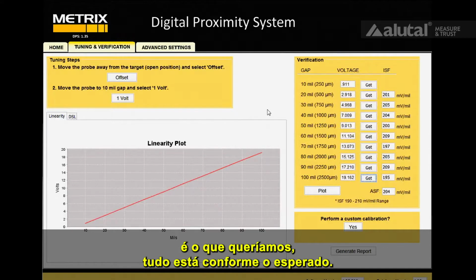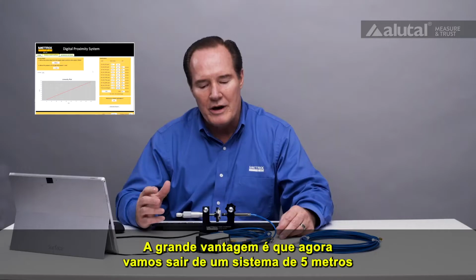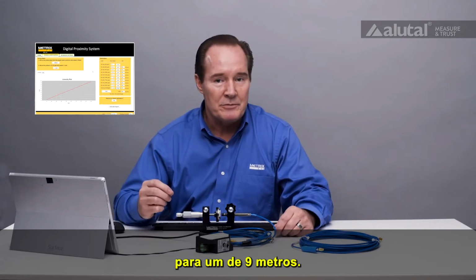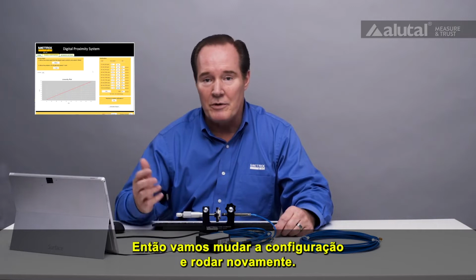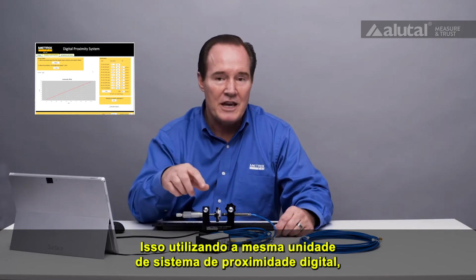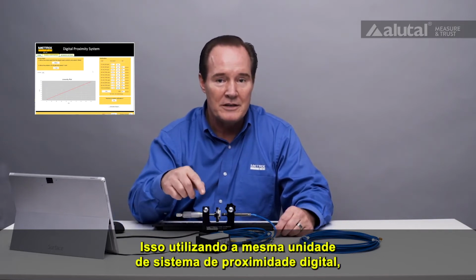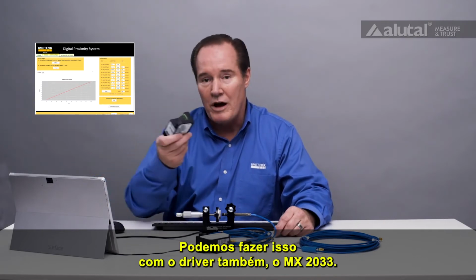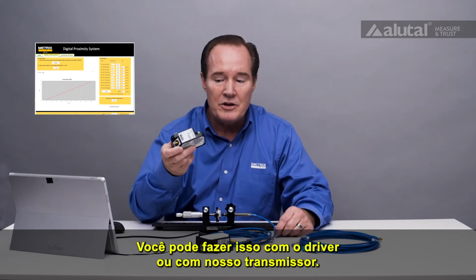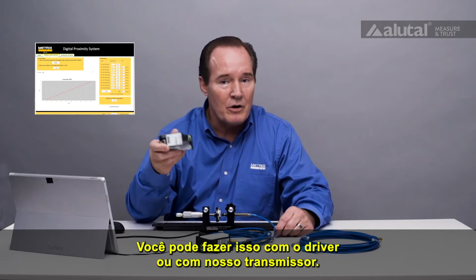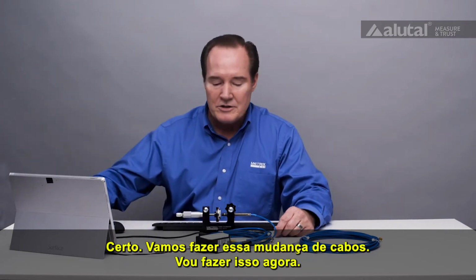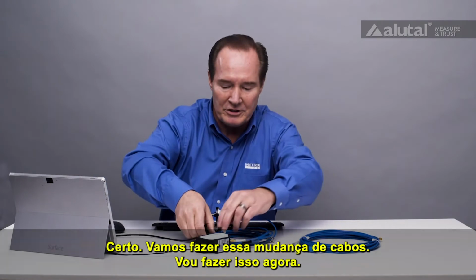Everything is within specification. It's what we wanted. Now what's great is we're going to go ahead and change this from a 5-meter system to a 9-meter system. Then we'll change the configuration and run it again. And that's with using the same digital proximity system unit, the MX2034. We can do this with the driver as well, the MX2033. So you can do this with either the driver or our transmitter. All right. So let's just go ahead and make that cable change. We'll go ahead and do that.